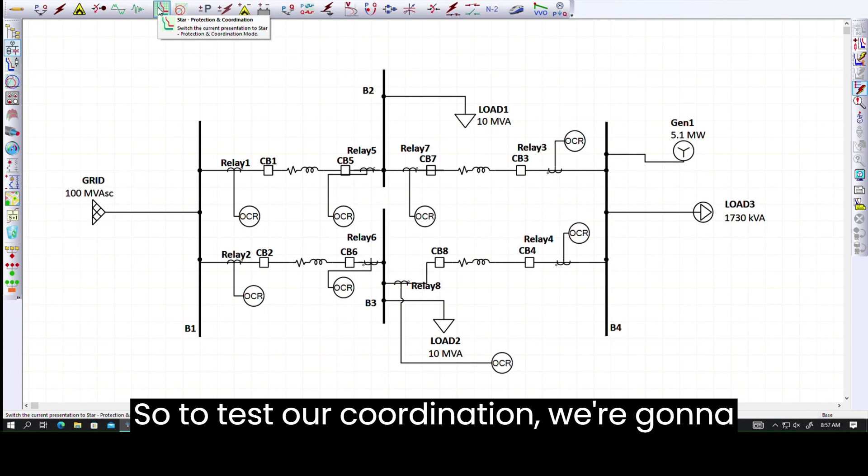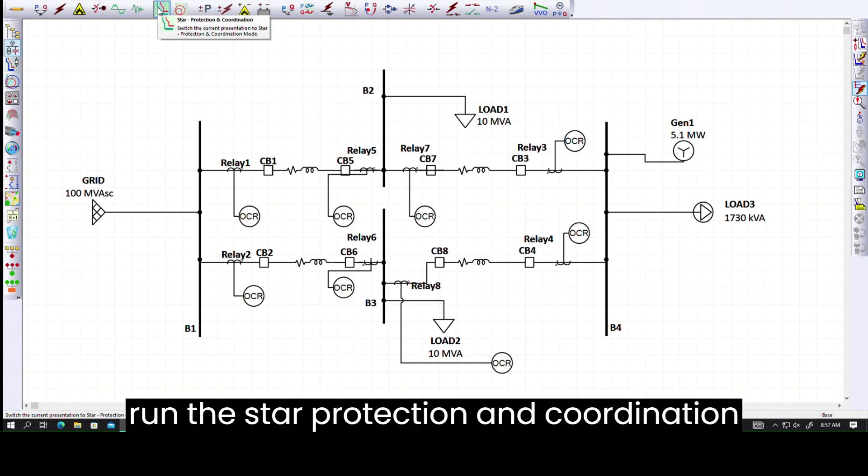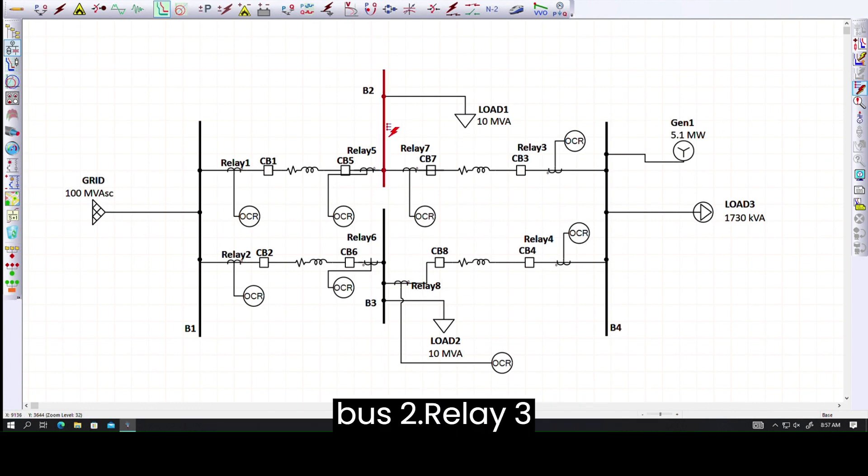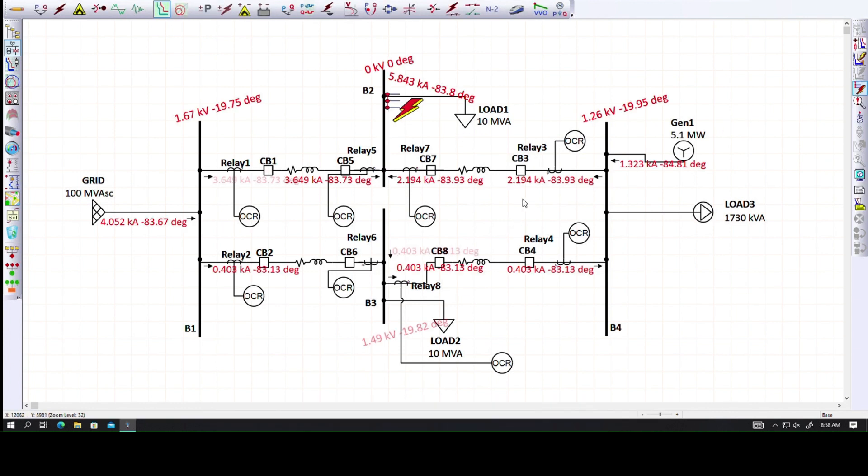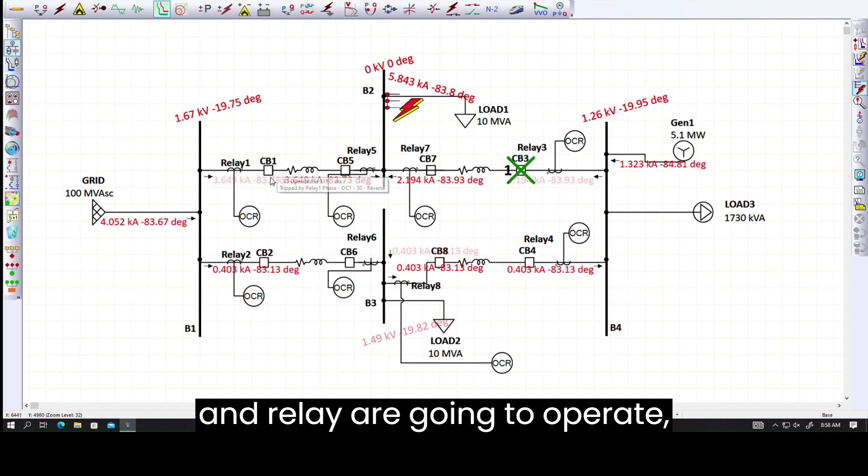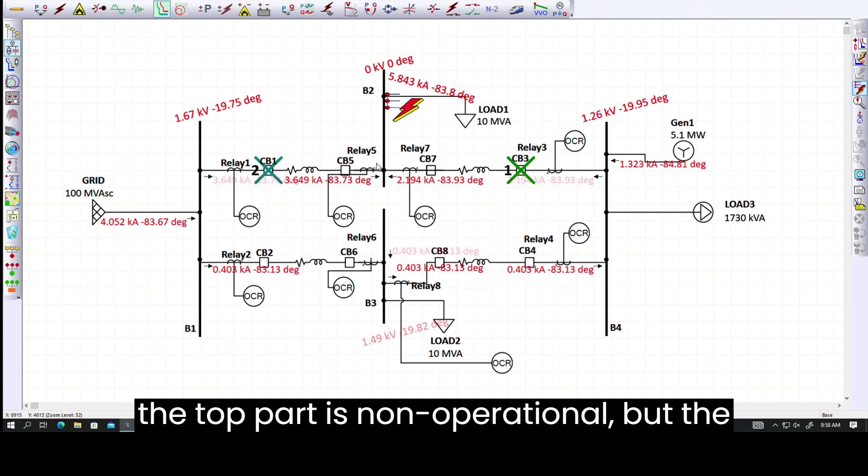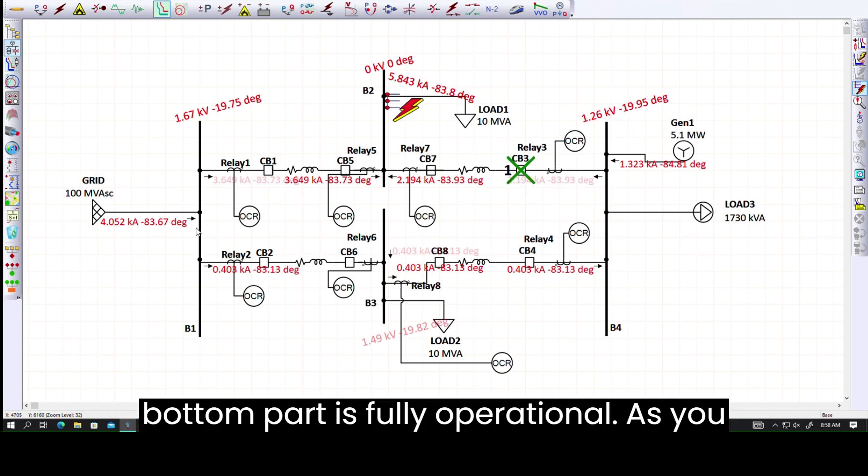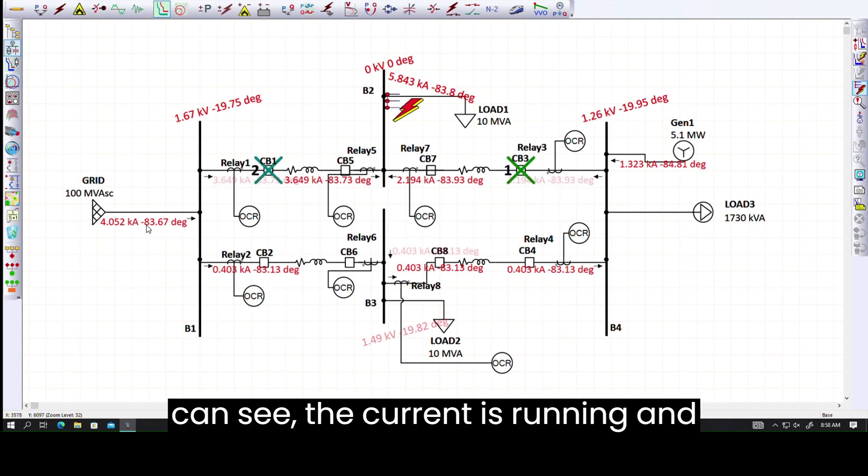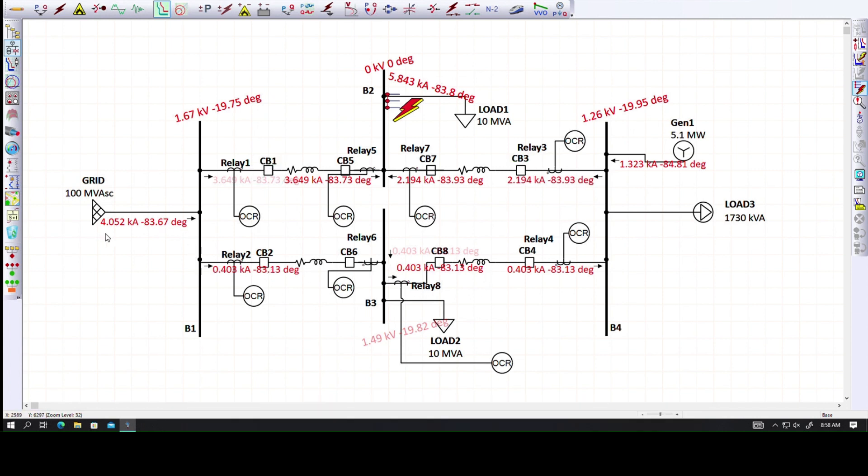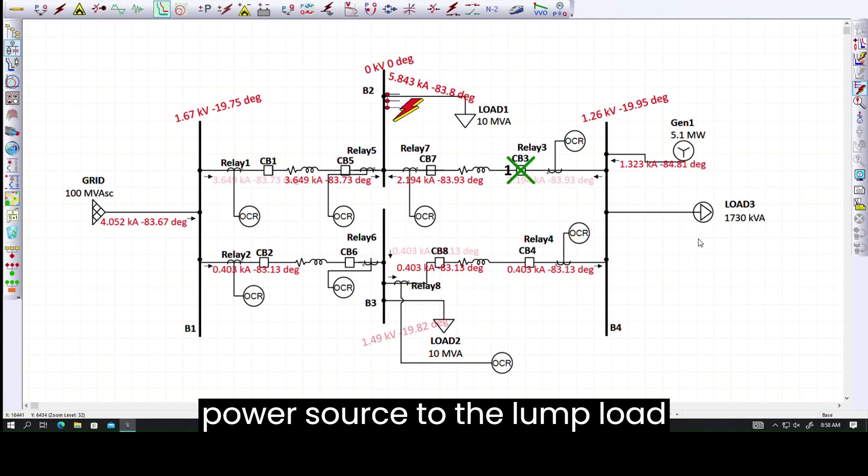To test our coordination, we're going to run the star protection and coordination study, putting fault insertion in bus 2. Relay 3 and relay 1 are going to operate, isolating the fault at the top part. The top part is non-operational, but the bottom part is fully operational. As you can see, the current is running and flowing here from the power source to the lump load successfully.